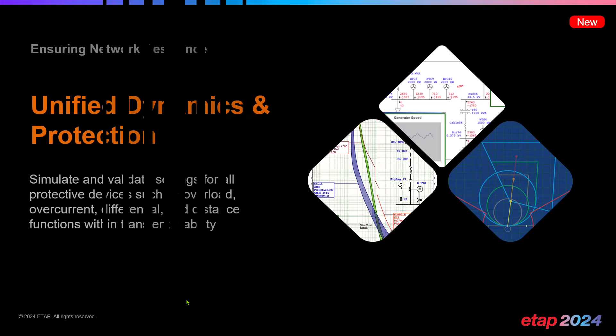One of the most exciting things is taking the enhancements to dynamics and combining and unifying them with protection. By doing so, we can simulate and validate the settings for all protective devices in ETAP 2024, such as overloads, overcurrents, differentials, and distance functions, which can include out-of-step relays within the transient stability module, all within the click of a single button.